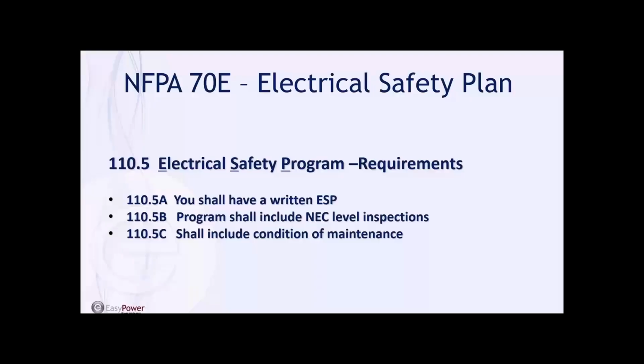5B says we shall inspect our systems related to NEC standards for new work. That can be expounded upon to ask, what about the rest of the building and the rest of the facility? When was there any type of audit or survey? In many buildings where we begin arc flash studies, there has been very little assessment of who's done that work or what anomalies or problems may exist across the full inventory of the electrical system. So although 5B focuses on new work and new projects, it's potential you could expand that to ask what should be done to audit the rest of the building as well.